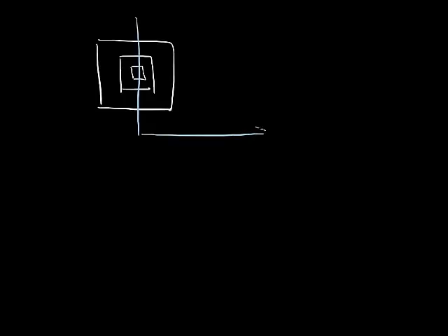Throw, as it relates to grills and diffusers, is the distance the air travels from the center of the grill or diffuser into the space. So let's draw a diffuser real quick. The throw distance is how far the air jet moves, measured from the center of the diffuser. As the air moves out from the diffuser, it'll also start to drop. So in side view, it may look something like this.